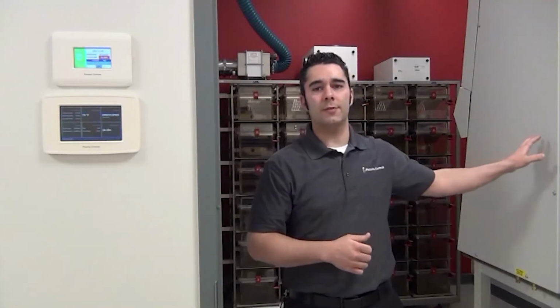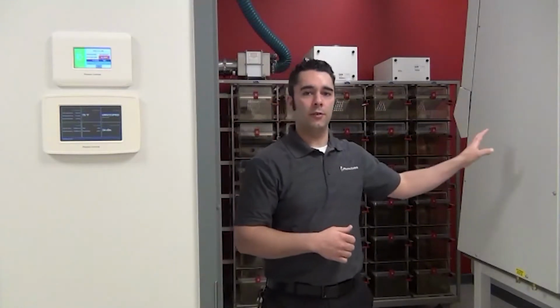The way that it works on this particular biosafety cabinet is that when the hood is shut off, the valve is shut off in its closed position. When you push the button to turn the fan on to recirculate air in this particular hood, the Phoenix valve will start to open. The hood itself actually has a velocity probe built into it. So as that Phoenix valve starts to open, the velocity will increase through the hood. As that velocity probe senses airflow going across it, then the blower will turn on to guarantee that you're not going to blow the chemicals or whatever you're using in this hood out the front of the hood. Again, making sure that the safety of the occupant is always paramount in this type of a situation.